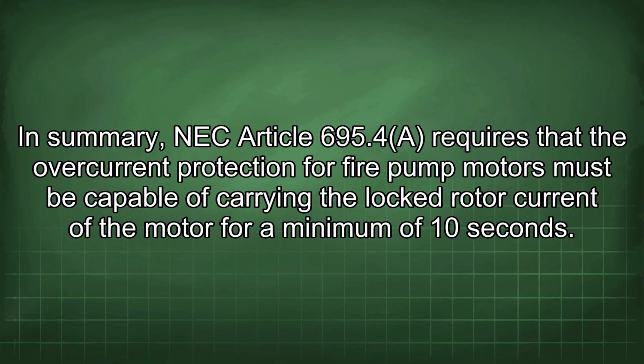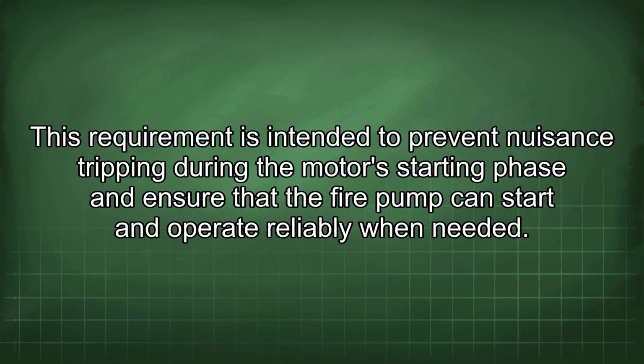In summary, NEC Article 695.4 requires that the overcurrent protection for fire pump motors must be capable of carrying the locked rotor current of the motor for a minimum of 10 seconds. This requirement is intended to prevent nuisance tripping during the motor's starting phase and ensure that the fire pump can start and operate reliably when needed.